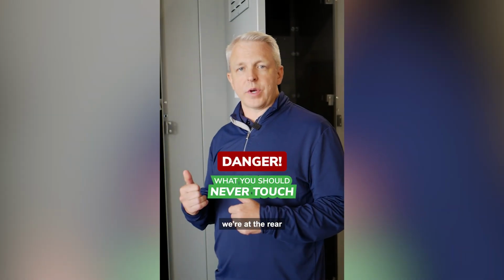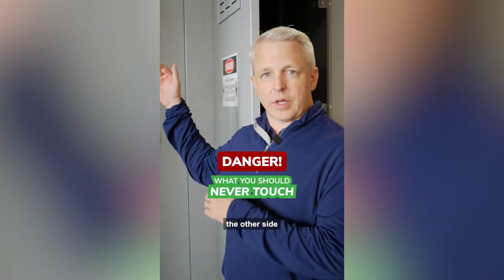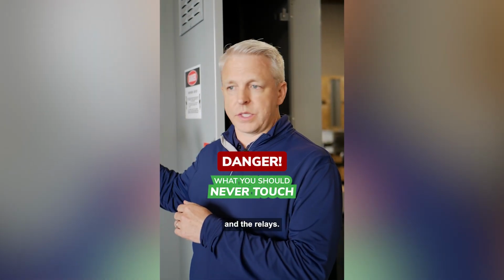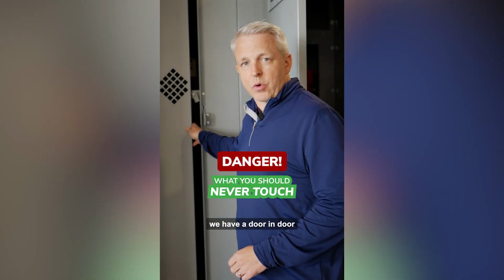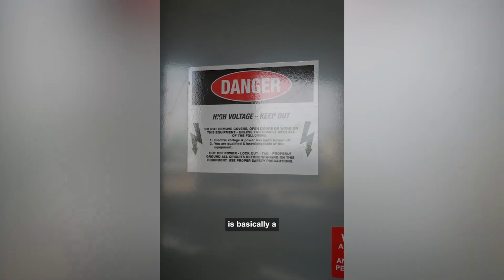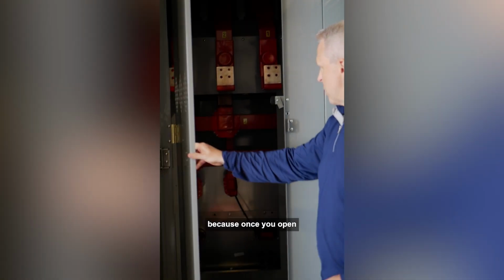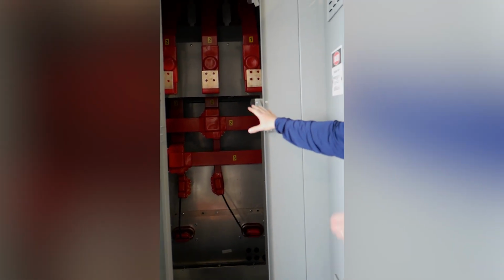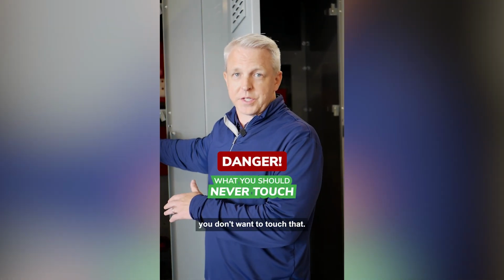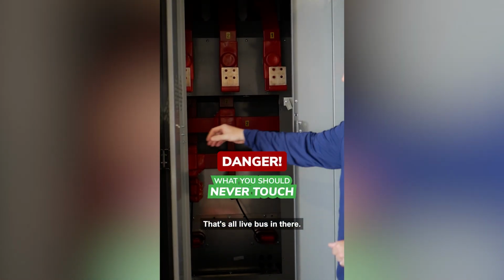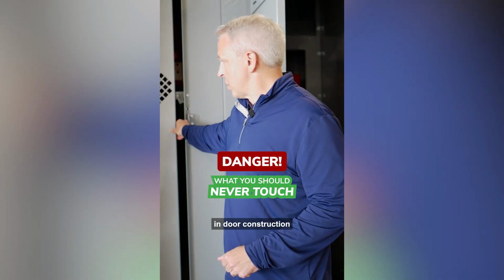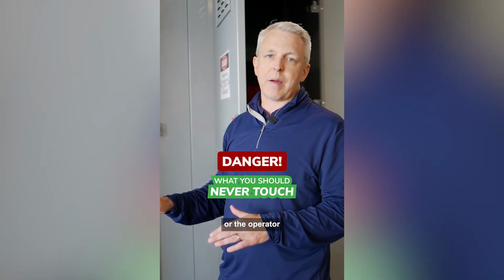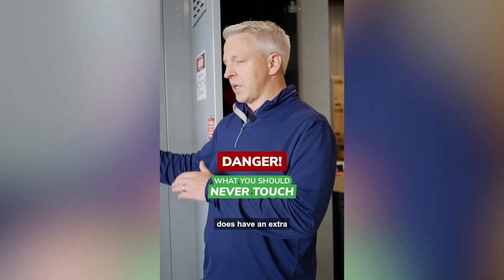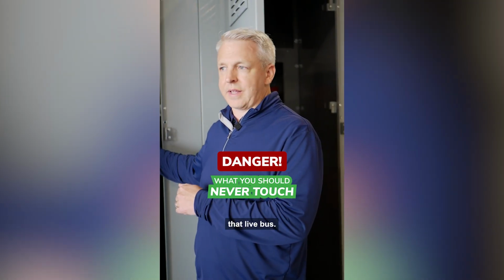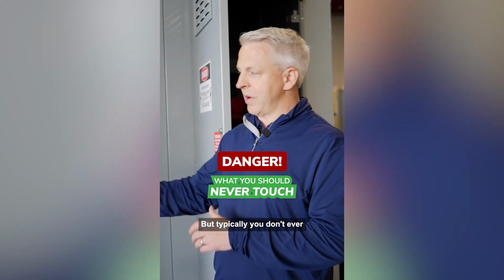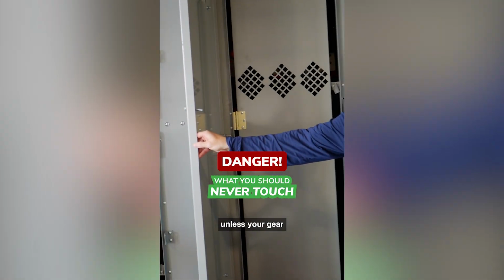Here we're at the rear side of a piece of metal-clad switchgear, so on the other side is the front face of the breakers and the relays. But back here we have a door-in-door construction. This door right here is basically a protective screening, because once you open that up, you're going to be exposed to live bus. Everything there, you don't want to touch. That's all live bus in there, so they typically have this door-in-door construction so that the personnel or the operator who's working on the switchgear has an extra layer of protection before he gets into that live bus. But typically, you don't ever even want to be opening this exterior door unless your gear is completely dead.